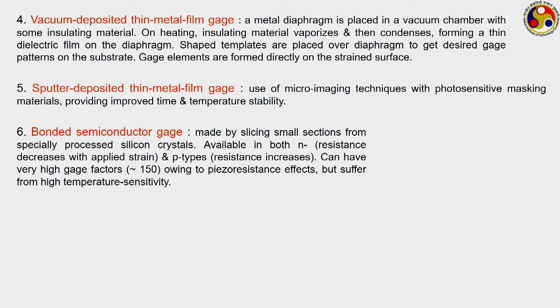The sputter deposited thin film gauges are an improvement on the vacuum deposition, where you use the IC manufacturing technology and micro imaging techniques with photosensitive masking materials. They can provide excellent time stability and also temperature stability. The biggest problem with any kind of strain gauge is the change in resistance with the temperature. Therefore, this temperature stability is very important, and some of these metal film gauges have much better temperature stability compared to the wire gauges. And the final two categories relate to the semiconductor gauges.